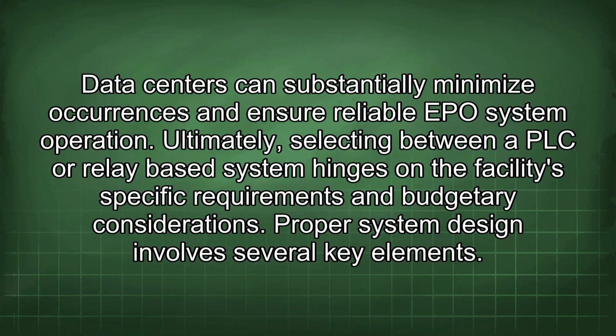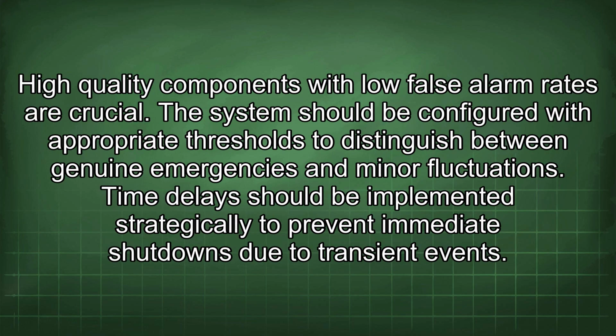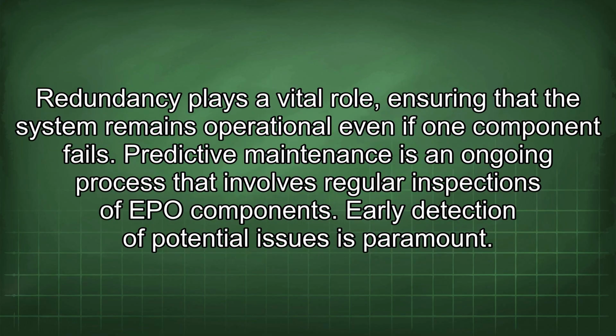Proper system design involves several key elements. High-quality components with low false alarm rates are crucial. The system should be configured with appropriate thresholds to distinguish between genuine emergencies and minor fluctuations. Time delays should be implemented strategically to prevent immediate shutdowns due to transient events. Redundancy plays a vital role, ensuring that the system remains operational even if one component fails.